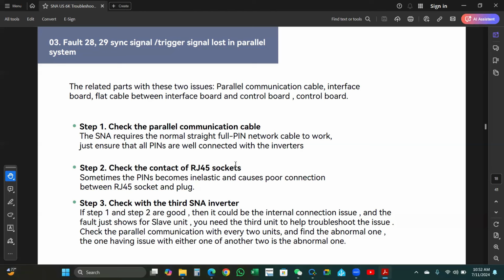Step three, check with a third SNA inverter. If step one and step two are good, then it could be an internal connection issue and the fault just shows on the slave unit. You need the third unit to help troubleshoot the issue. Check the parallel communication cable with every two units and find the abnormal one. The one having an issue with either of the other two is the abnormal one.